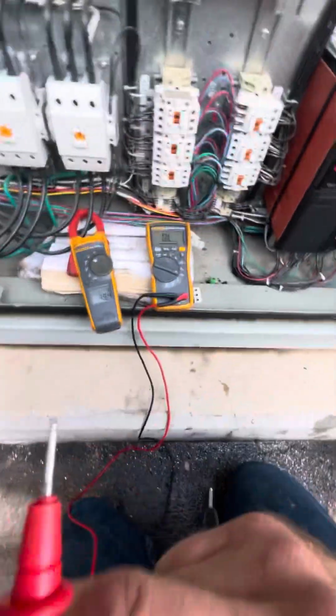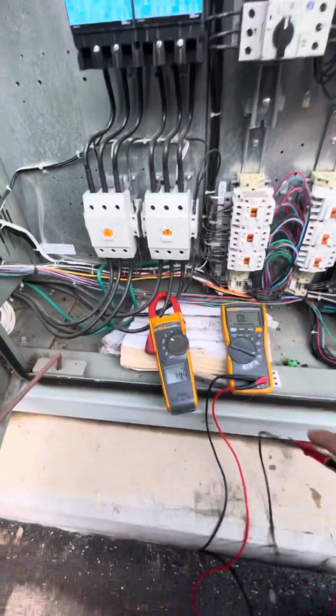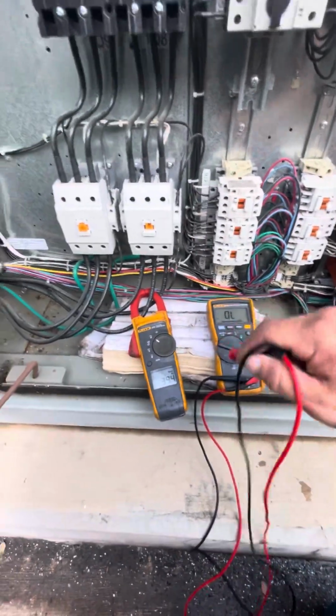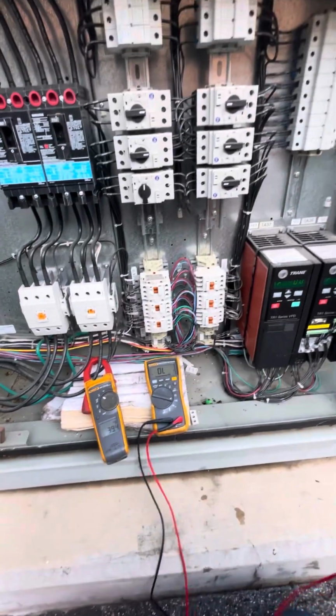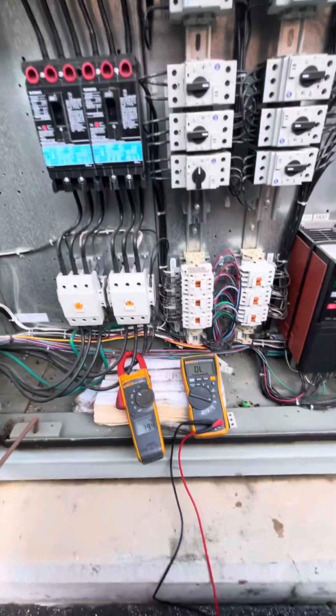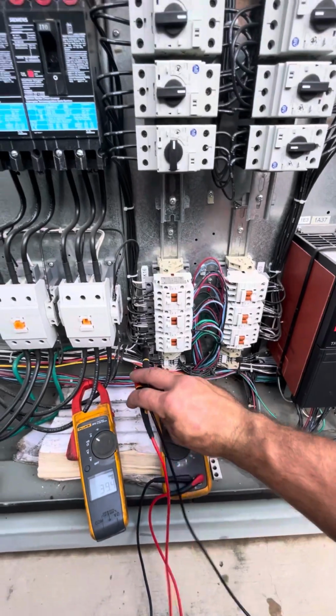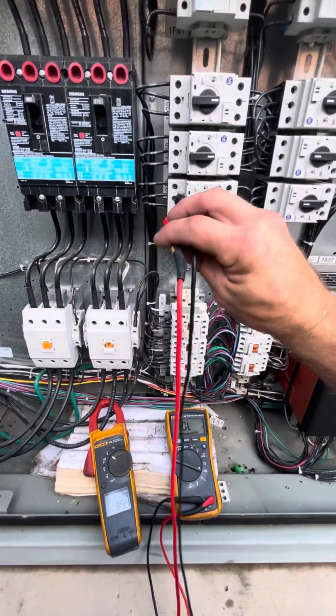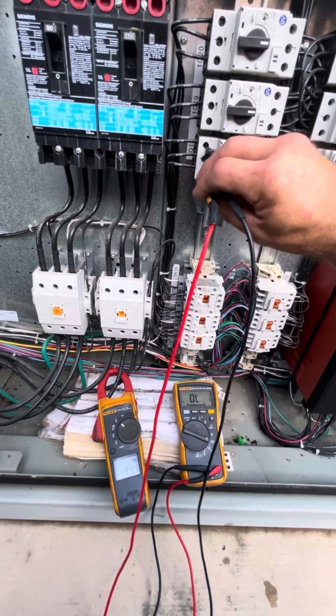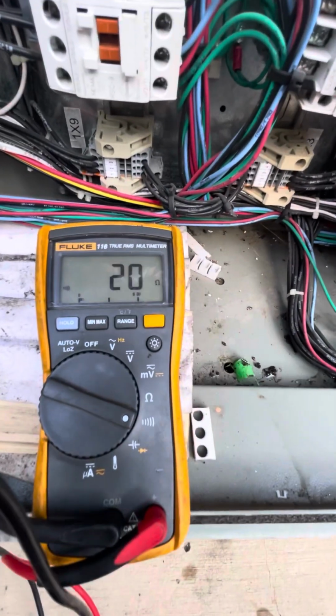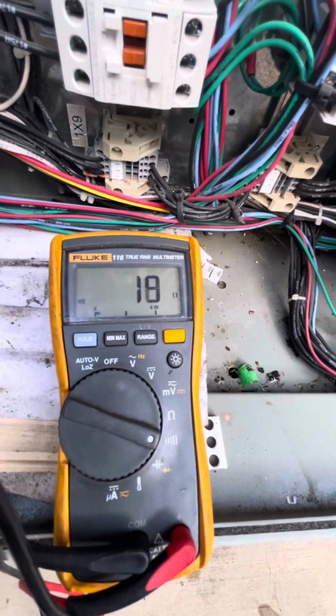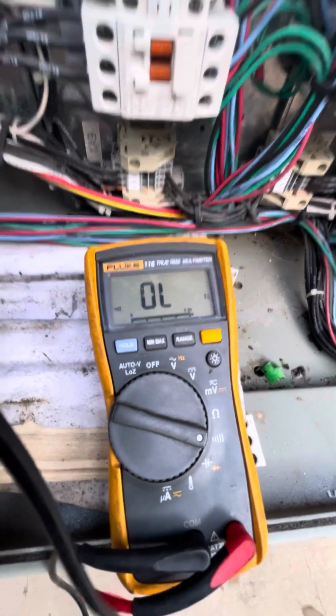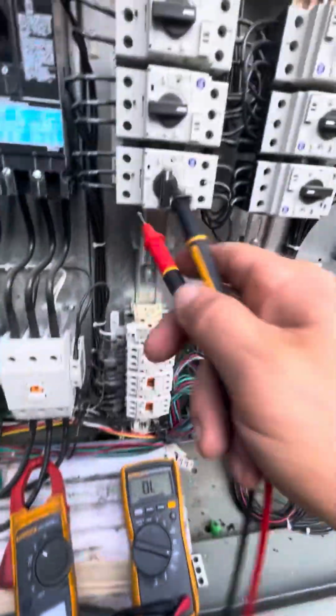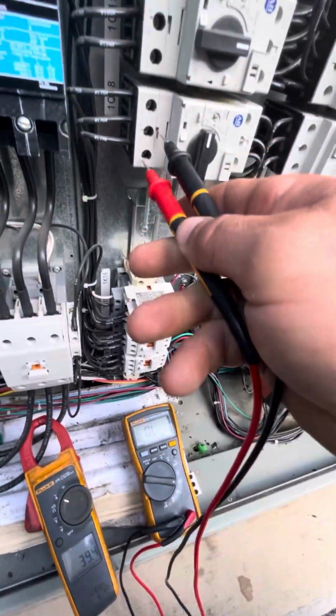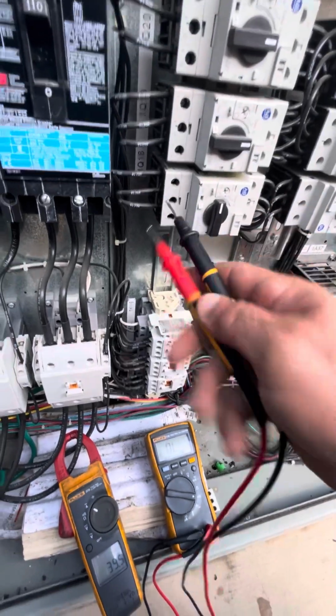I've got another Fluke, a 373, here for amps. If I have to use anything here or there, we've got one to reference the other in case somebody doesn't believe me. So what we'll do here, since this contactor's pulled in, we trace this to here, and we're going to test this out. We're not hot on this side, so we're able to do a resistance test there, a tone test. We might have a little voltage leak through, so that's probably less than ideal. Normally you're going to get a solid ring. Yeah, I think we've got some tone issues there. We've probably got voltage on it.